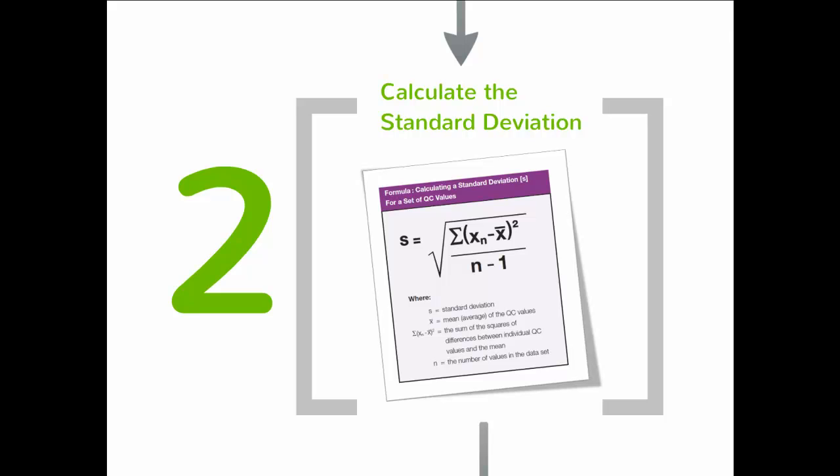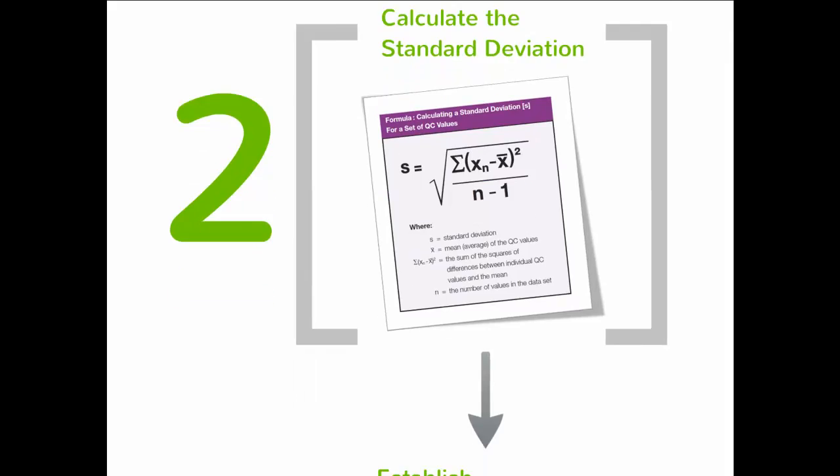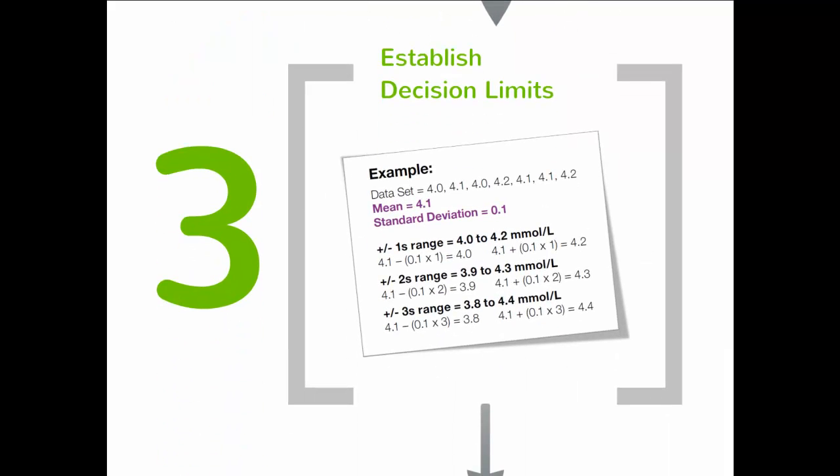Using the mean and standard deviation, the laboratory can establish decision limits. These limits are used to define what is considered an acceptable control result. Decision limits are established at ±1s, 2s, and 3s from the mean.